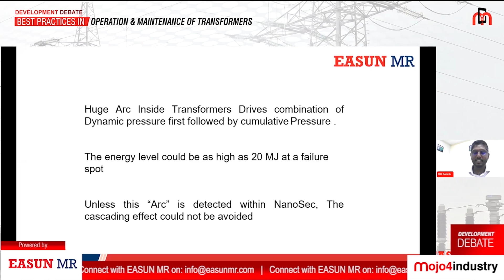See, there are 3 stages of protection we offer. When there is a fire possibility in a transformer, generally the fire starts from the arc. First the arc starts, and then the arc becomes an intensive arc, then it converts to fire. We catch the arc within 5 milliseconds, within an average of 8 milliseconds, and it gives a command to the breaker. This is stage 1. So we catch it at the initial stage.